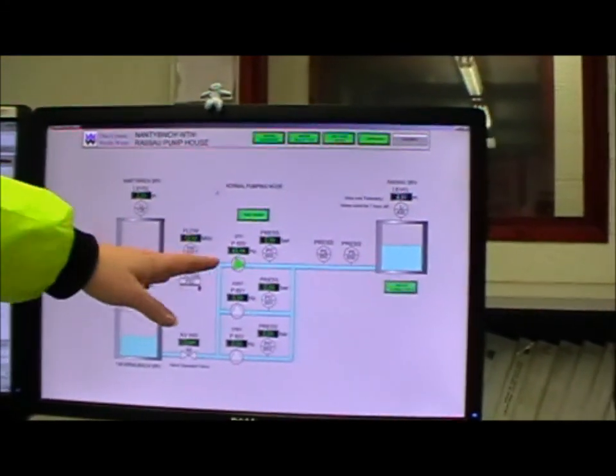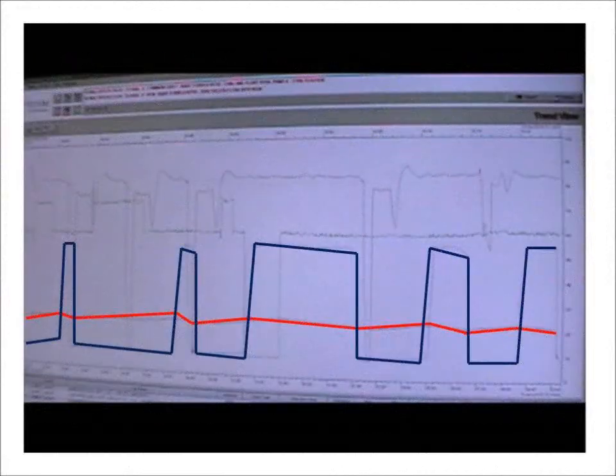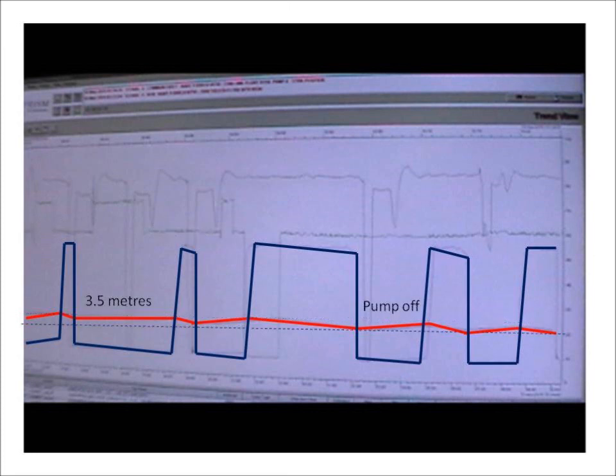We then need to get that water out to distribution, and we control this on numerous set points. We have the water in the final water tank. Here we have a pump running, which can be shown by this green line. The flow meter downstream of the pumps shows when the pump is running. When the reservoir fills to a set point, the pumps automatically switch on to fill the reservoir downstream. When the reservoir drains down to a set point, the pumps switch off. This is to provide reservoir turnover and to prevent bacteriological failures. However, water companies aren't very good at this process, as they like to keep the tanks full for operational reasons.